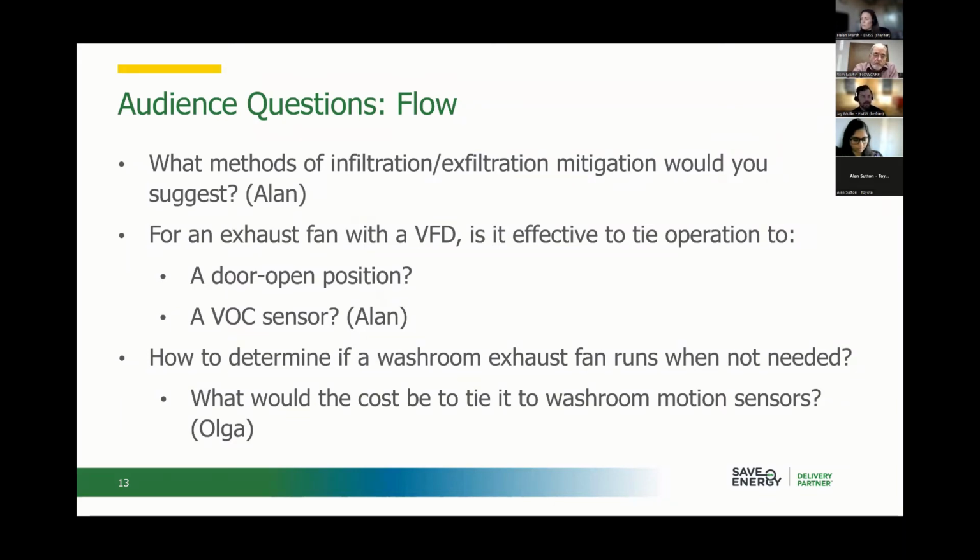Okay. Thanks. And then we had a question from Olga about how to determine if a washroom exhaust fan runs when not needed. This would be in a commercial retail situation. And what would the cost be to tie the exhaust fan to the washroom motion sensors or occupancy sensors in there? So the first part of that, how to determine if it runs when not needed, I guess it's like anything else out there, trying to get a trend on what's going on with it right now.